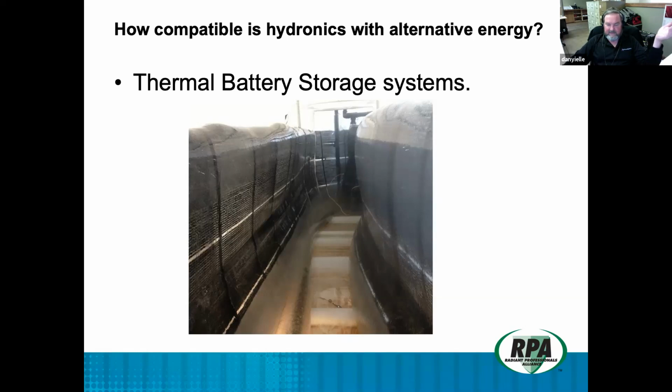which can include the outside air, an active solar panel. It could be a ground source heat pump. If you've got a vertical borehole well that you're running water into a house, that water is coming in at 40 degrees, so it's greater than 32, so it can help melt the ice. Snow melt system on a driveway, that's a huge solar collector. You can extract the heat off of that driveway and put it into this storage tank and remelt that ice and raise the storage tank temperature again. And I really feel that there's a huge future in the system. The most expensive component on a ground source heat pump system is the vertical boreholes. This is going to eliminate probably 75% of the required boreholes on a lot of systems. So watch for this to come to the forefront in the near future.